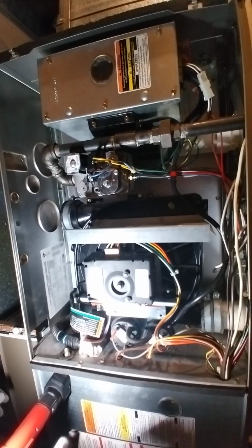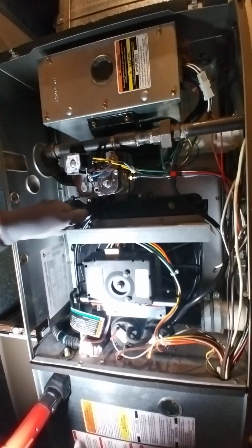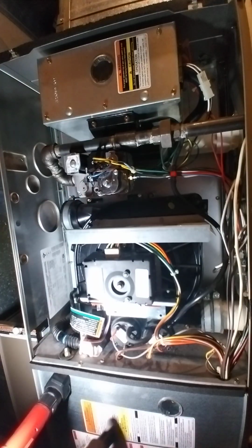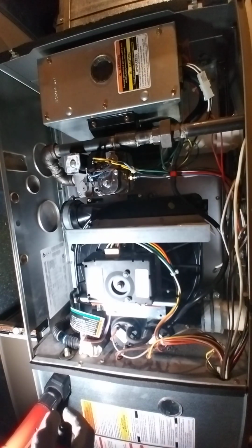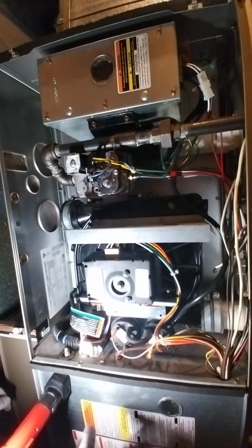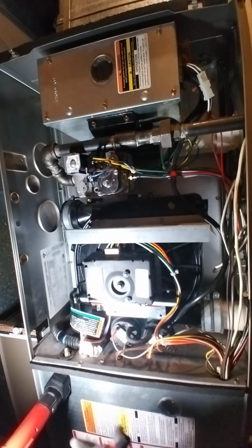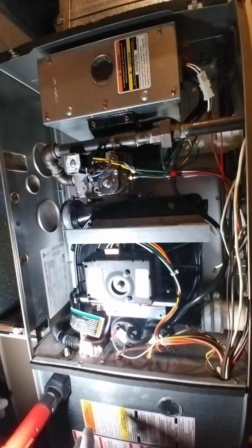So I started going down other troubleshooting rabbit holes. The first thing I ended up checking was the high temperature sensor itself, which is hiding behind here. So I threw a multimeter on there and ran the furnace to see if it was ever opening up, because that sensor is in series with a lot of the functions of the furnace. If that self-resetting sensor ever trips, it's going to cut the gas. It's going to cut the signal to the control board saying that nothing is going well right now.